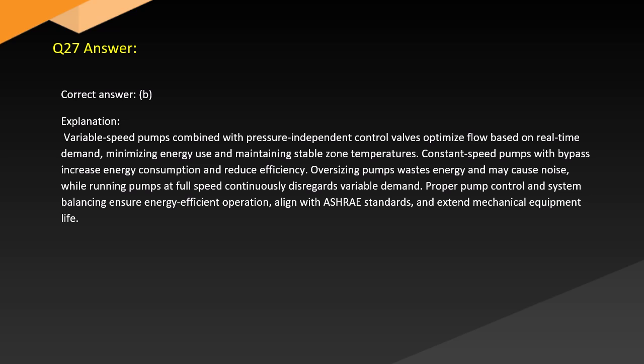Answer. Correct answer. B. Explanation. Variable speed pumps combined with pressure-independent control valves optimize flow based on real-time demand, minimizing energy use and maintaining stable zone temperatures. Constant speed pumps with bypass increase energy consumption and reduce efficiency. Oversizing pumps wastes energy and may cause noise, while running pumps at full speed continuously disregards variable demand. Proper pump control and system balancing ensure energy-efficient operation, align with ASHRAE standards, and extend mechanical equipment life.